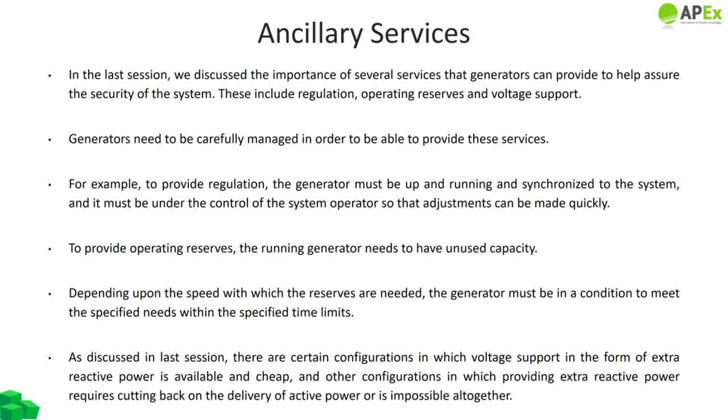An important consideration in unit commitment is the provision of ancillary services and reserves. We discussed in the last session the importance of services like regulation, operating reserves, and voltage support that generators provide to assure system security. To provide regulation or reserves, a generator must be up, running, synchronized to the system, and under the control of the system operator. To provide operating reserves, a generator cannot already be at maximum capacity — it must have unused capacity and be able to respond within specified time limits. The optimal unit commitment decision must also account for the need for these ancillary services.